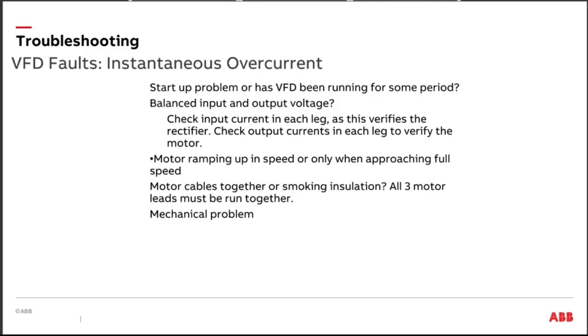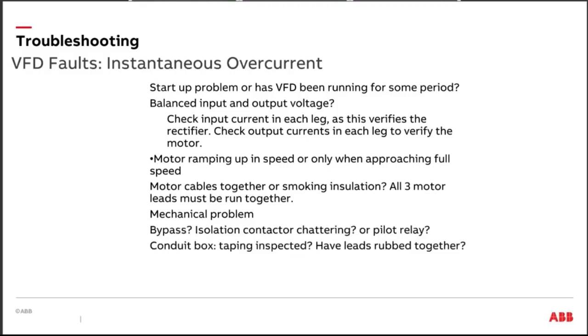Is there any chance in the world? Do you know the electrician that wired the pecker head? Do you know this person? Are you comfortable that the motor's not been vibrating, and that you did maybe a poor taping job, and those motor leads have chaffed inside that pecker head, and we're starting to see something like that happen? Okay, those are the kind of things I think about. I like to think about the application itself, and then the motor leads, and I think the last thing I think about is the variable frequency drive. Okay, that's kind of how I would typically troubleshoot instantaneous overcurrent.